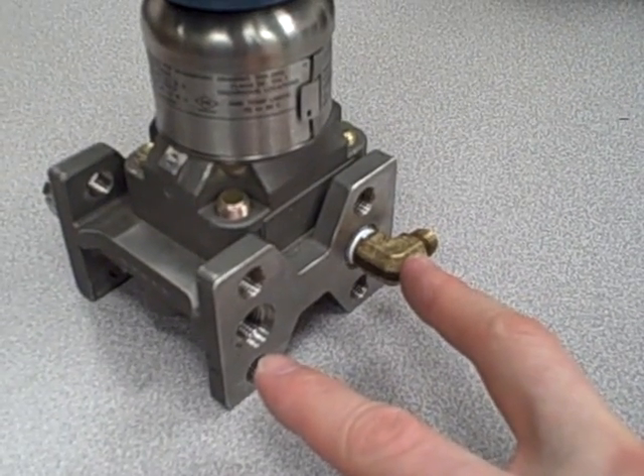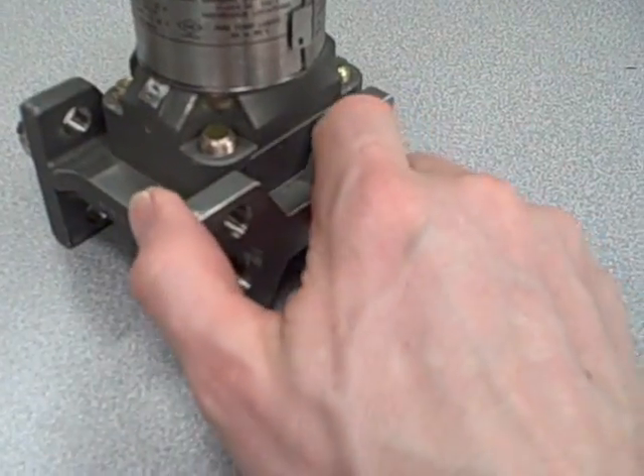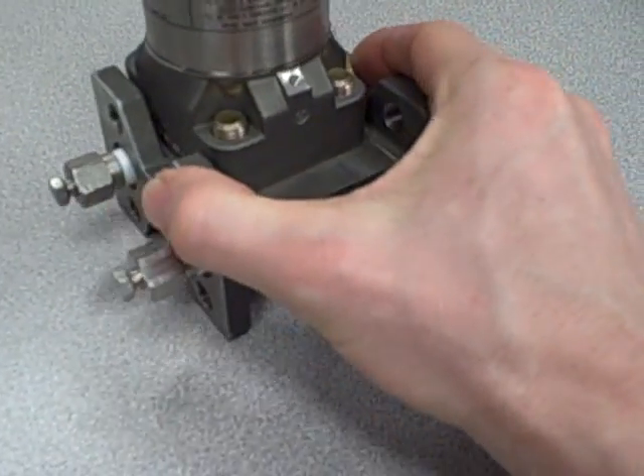But before you take this transmitter completely out of service, you need to vent whatever stored pressure may reside inside the manifold assembly. And that's what these are for.